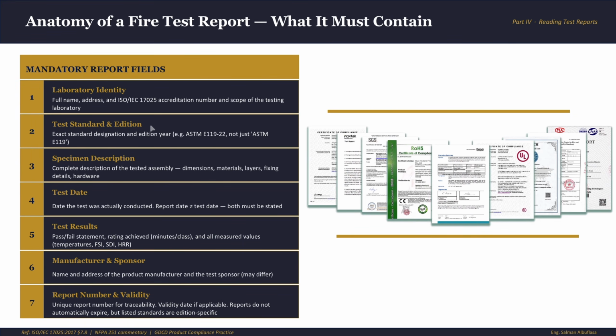And second, test standard and edition. Not ASTM E119, no, it's ASTM E119-2022 or 2025 or the latest edition by the time you watch the video. The year matters, and always check the edition year. And then the specimen description. Every material, every dimension, every fixing detail, if anything on site differs from the description, the report does not cover it.